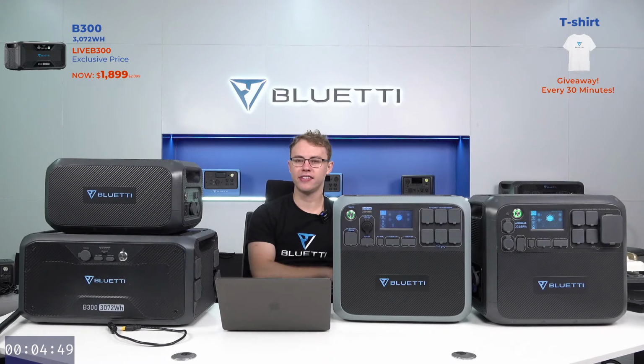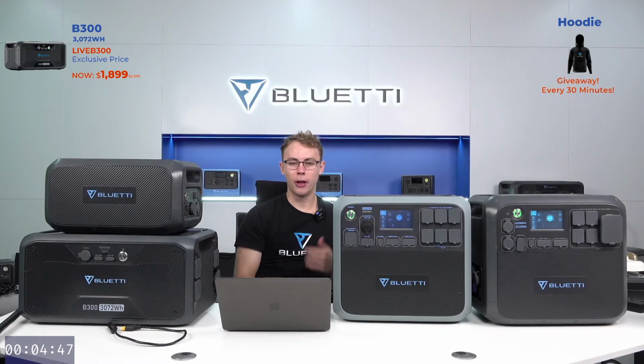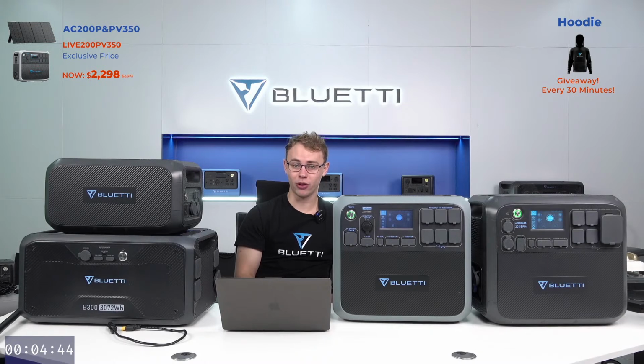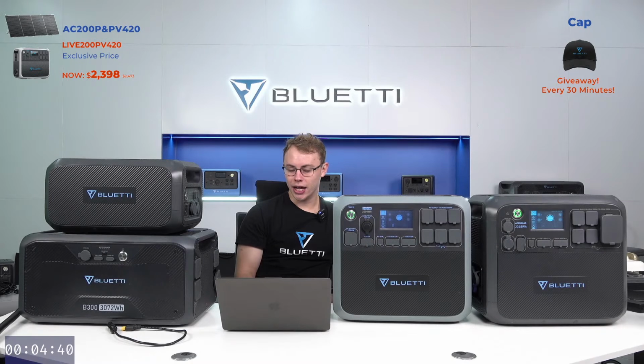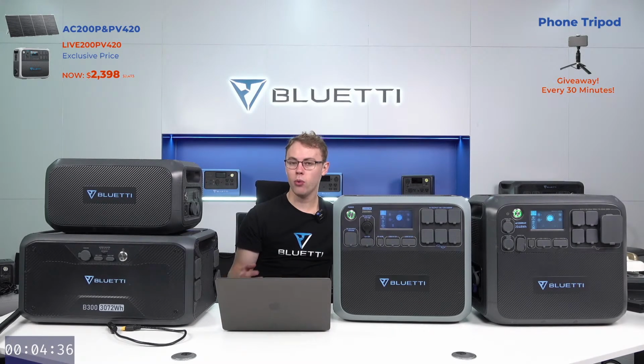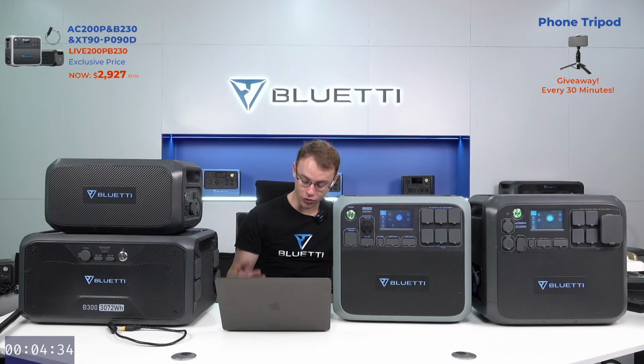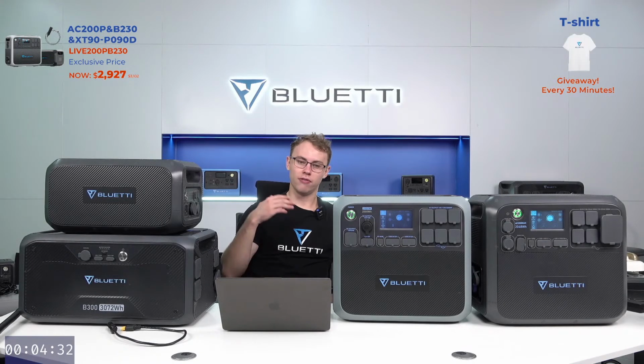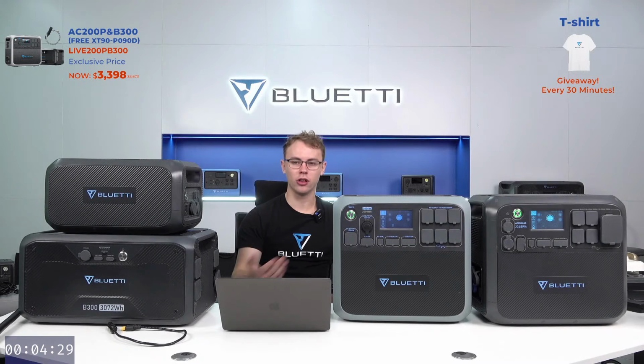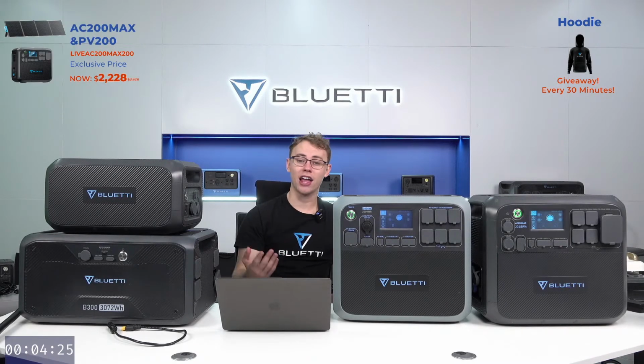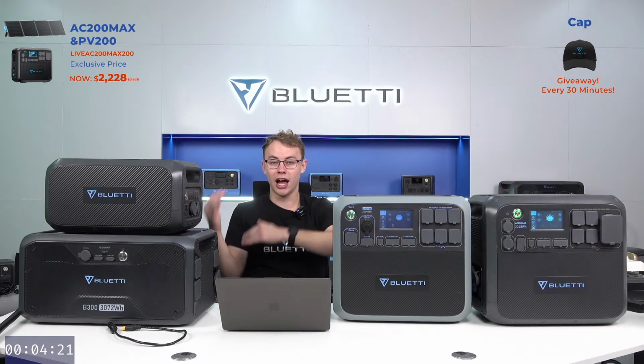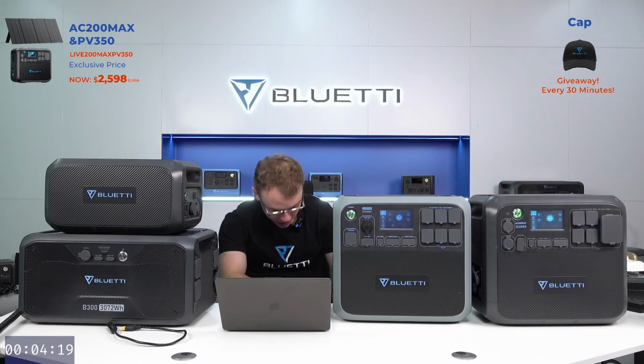Also remember, when you connect panels in series, voltages add up. So let's say you connect it to our PV 420 solar panel, which is like 44.3 volts. With one PV 420, it's okay. With two PV 420 panels, voltages add up, still good. But if you connect 5 PV 420 solar panels, you cannot do that, because the voltage would add up and exceed the allowed limit.